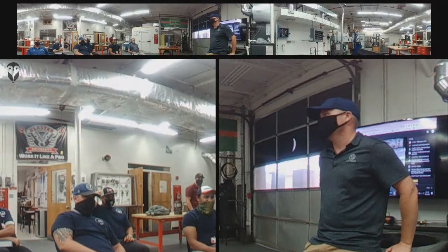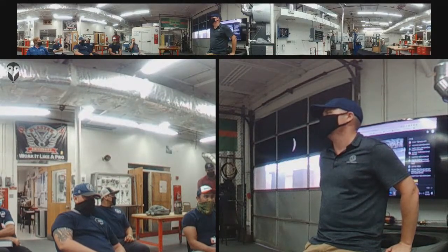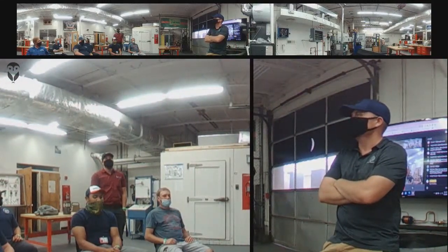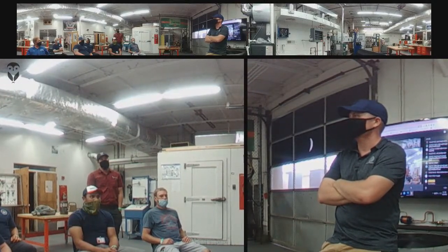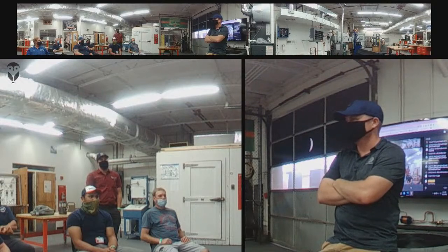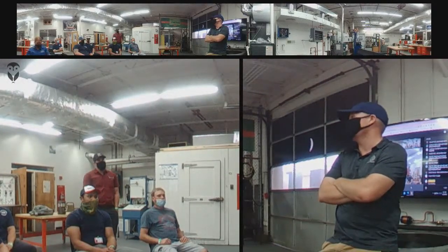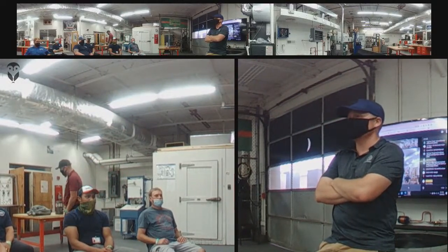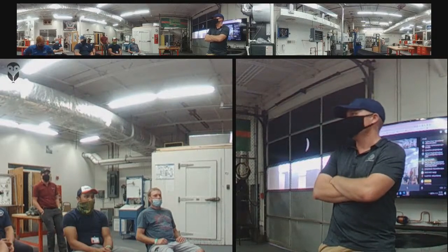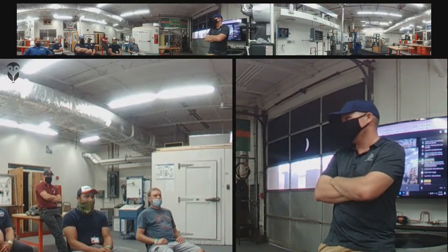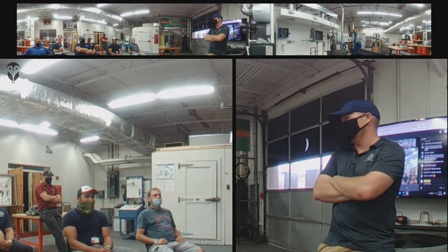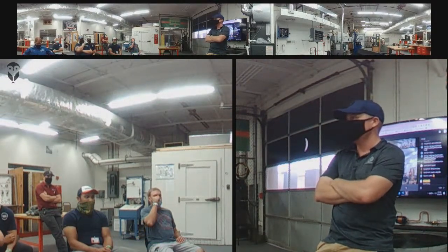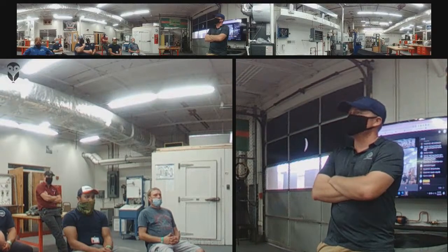No interesting stuff. Nothing. I had a tech call me today. Heat strips were running in full mode. He narrowed it down to a short in the chase between Y and W, causing those to run. Yep, that'll do that. Now, is that actually a short? Here's the question. That is a short. That's always a thing, because when we say short, a lot of people will say a short is a circuit that results in high current, blowing a fuse or tripping a breaker. But in this case, it's a short between two switch legs, both powering different loads. So there are things connected that shouldn't be connected.